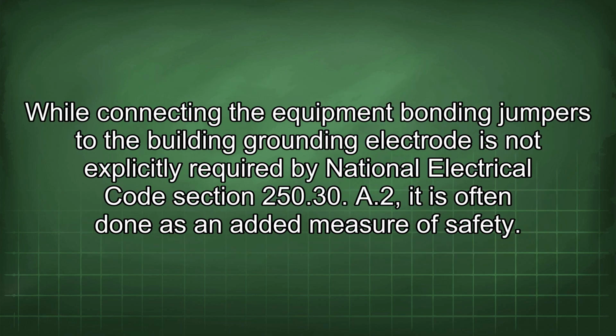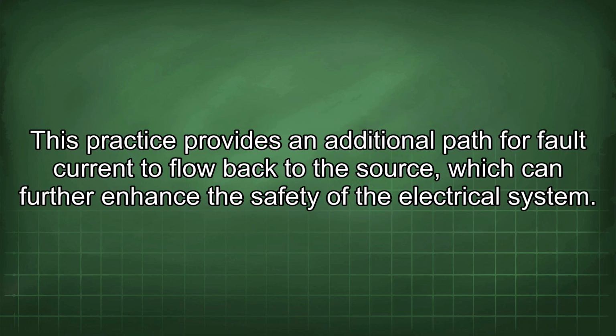While connecting the equipment bonding jumpers to the building grounding electrode is not explicitly required by National Electrical Code Section 250.30(A)(2), it is often done as an added measure of safety. This practice provides an additional path for fault current to flow back to the source, which can further enhance the safety of the electrical system.